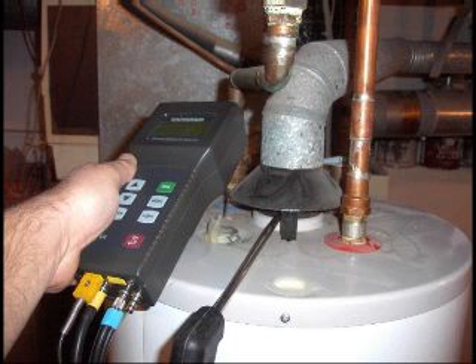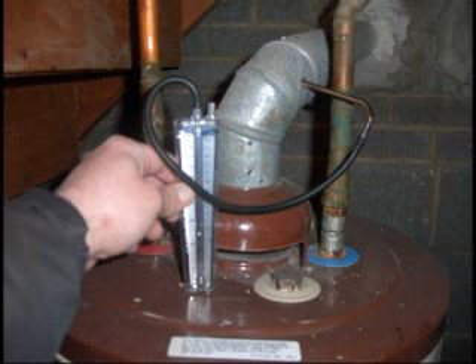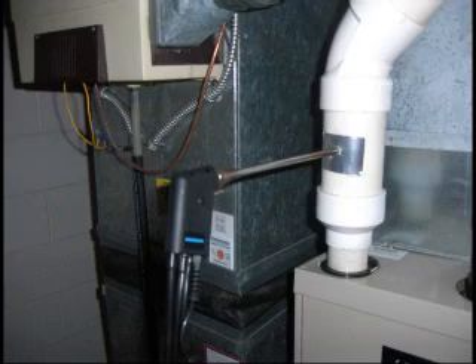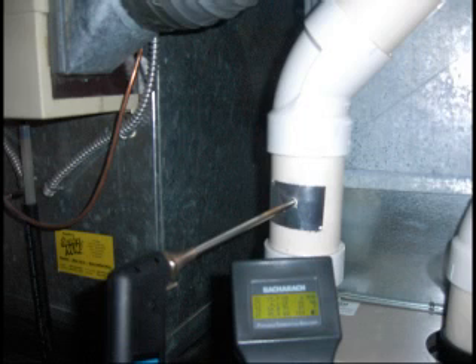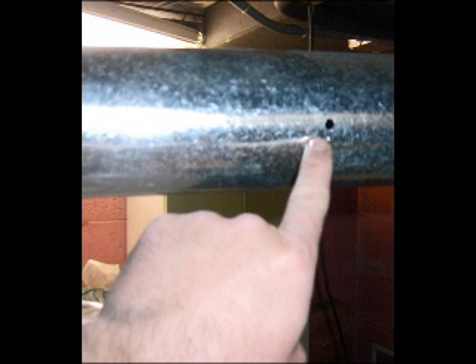You can tell if a furnace or water heater has been tested for combustion draft simply by looking at the flue vent that leaves the unit. There's usually a small hole drilled through it, because that's how they have to insert their probe. It's either left open, you don't really have to patch those holes, or it's been patched with high temperature caulking or tape.